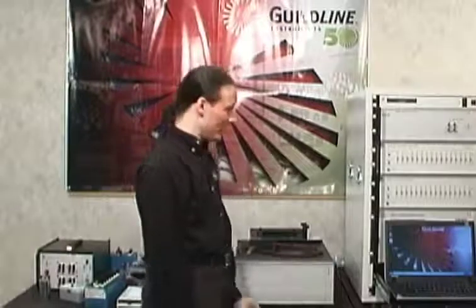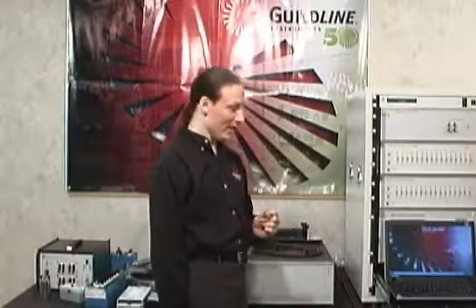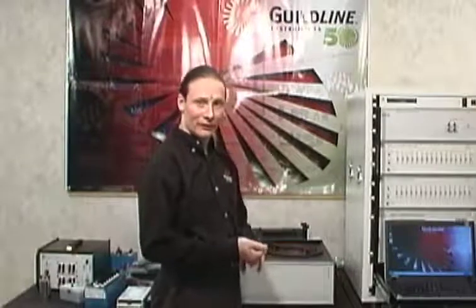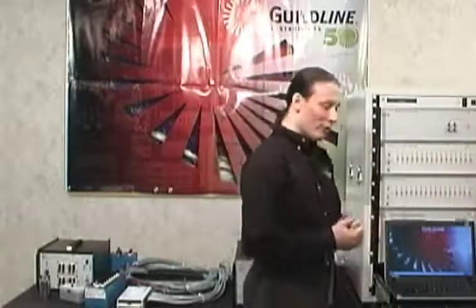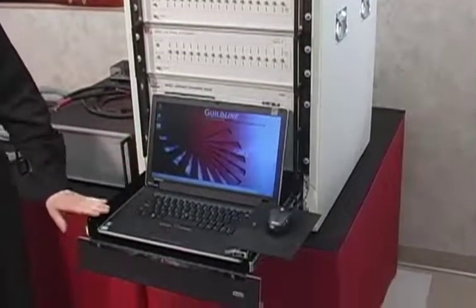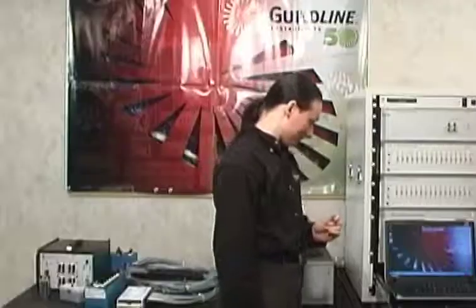Today we're going to be discussing BridgeWorks, which is the software that is included with the 6625 system and is designed to automate and control all the features and functions of the system to simplify a lot of processes and take care of things such as data logging and your mathematics and generating all your certs. The software itself is running on a system controller, which is the laptop provided with the system here in the laptop tray. And it's running on a Windows 7 platform.